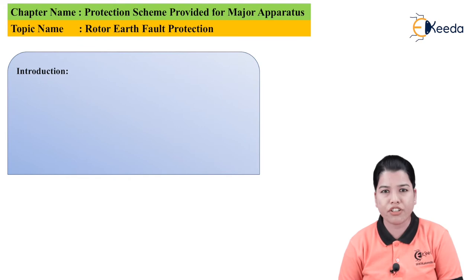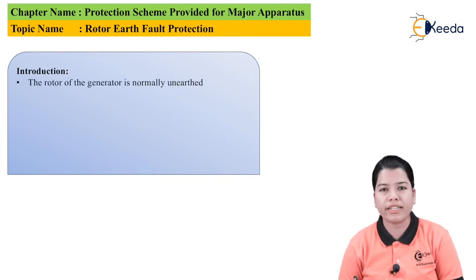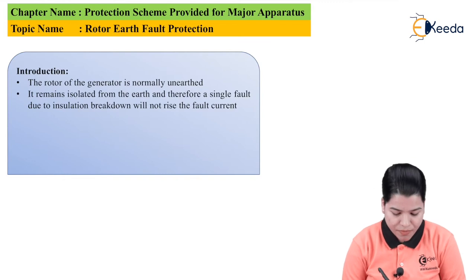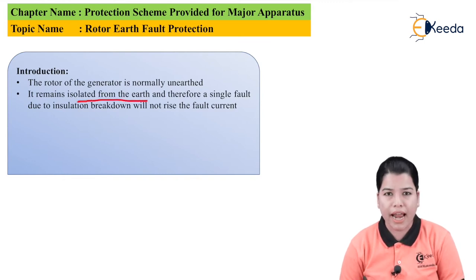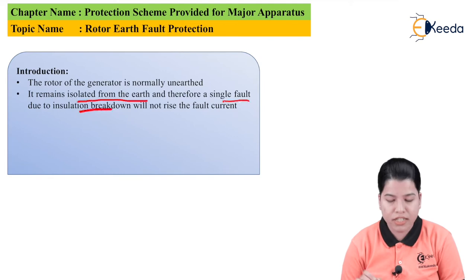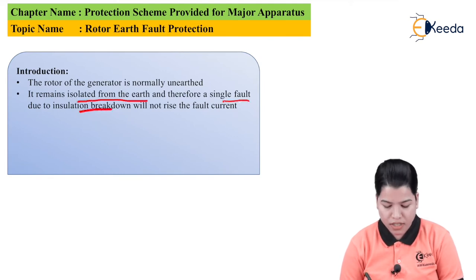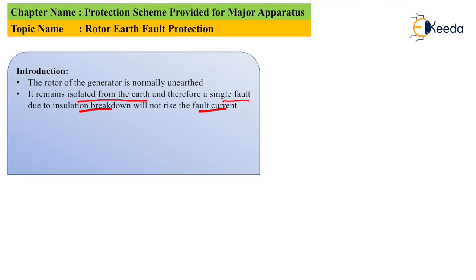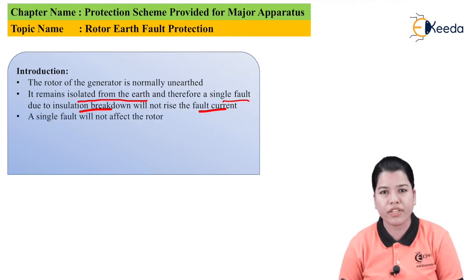First, let us study the introduction. Basically, the rotor of the generator is not connected to earth — that is, it is unearthed. Therefore, it remains isolated from the earth, and a single fault due to insulation breakdown will not cause a rise in fault current. So, if one fault occurs due to breakdown of insulation, it will not be considered as a rise in fault current because the rotor is not earthed. A single fault will not affect the operation of the rotor.